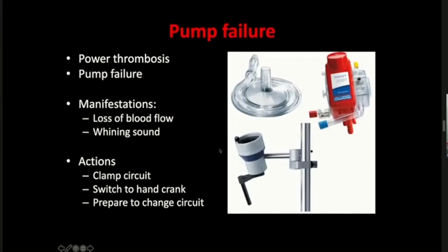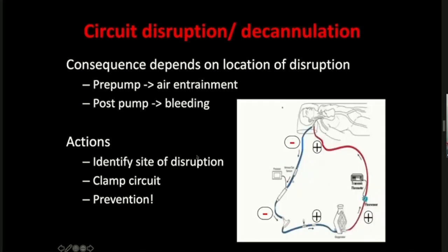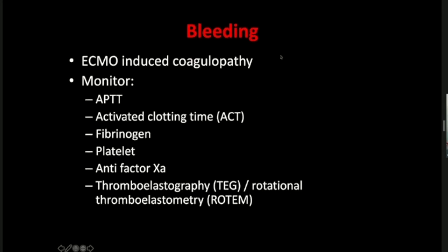Other complications: pump failure, which we have discussed, is a mechanical failure — if rotated to an ICU with an ECMO patient, always find out how to perform hand cranking. Circuit disruption and decannulation are catastrophic; immediate action is to clamp the line, stop the pump, commence rescue ventilation, and quickly call for help to re-establish a new circuit. Bleeding is a common complication — at or outside the site of cannulation — with catastrophic sites being intracranial, GI, and retroperitoneal. Intracranial bleeding is usually life-limiting and may require consideration of withdrawal of ECMO. The ECMO circuit itself can induce a coagulopathic state. If bleeding occurs, we may need to correct coagulation components, top up platelets, and replace fibrinogen. Products affecting factor Xa or protamine are rarely given as they can cause catastrophic circuit thrombosis.